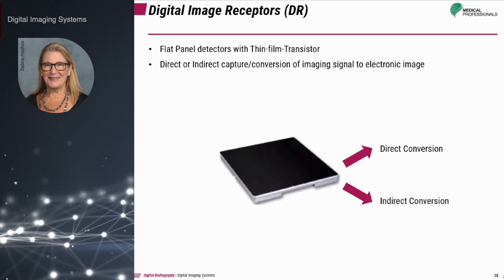The difference between direct and indirect capture is whether or not a scintillator material is needed. Direct capture flat panel detectors use a photoconductor, which converts exit radiation into an electronic signal. Indirect capture flat panel detectors need a scintillator material to capture the remnant beam and convert X-ray photons into light photons — a two-step process: first converting X-ray photons into light photons, then converting those light photons to an electronic signal.